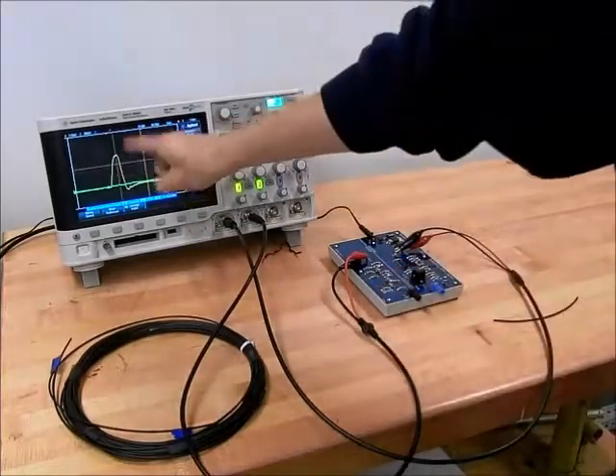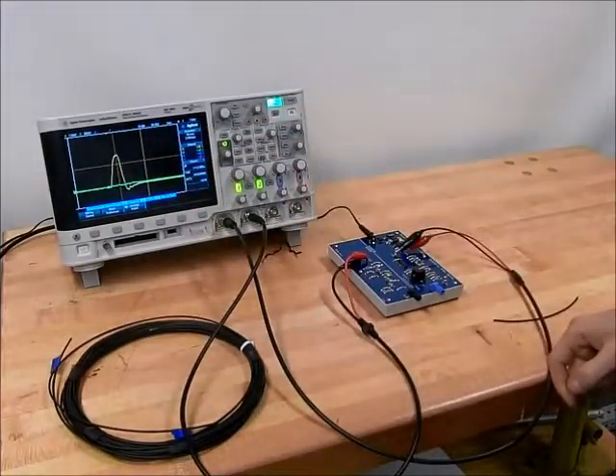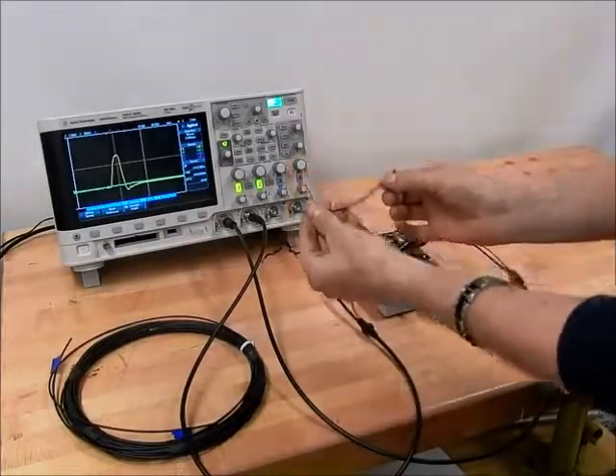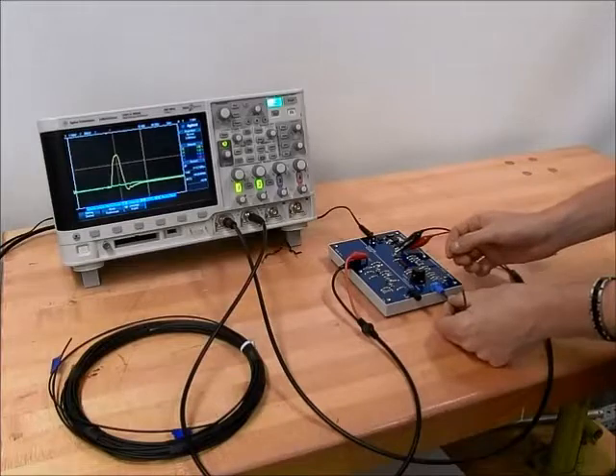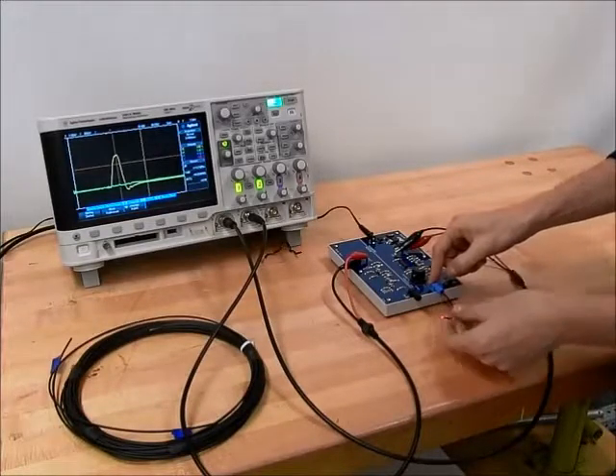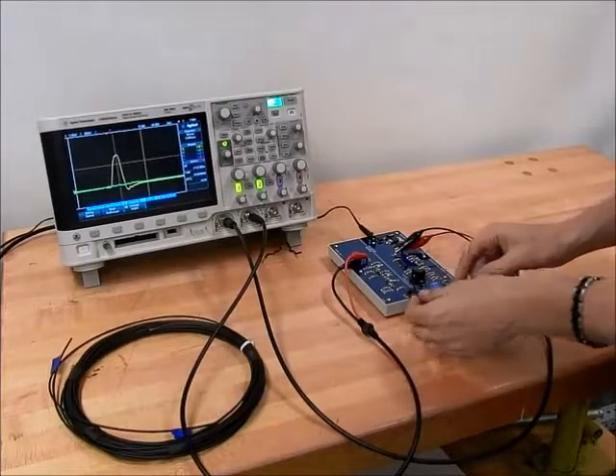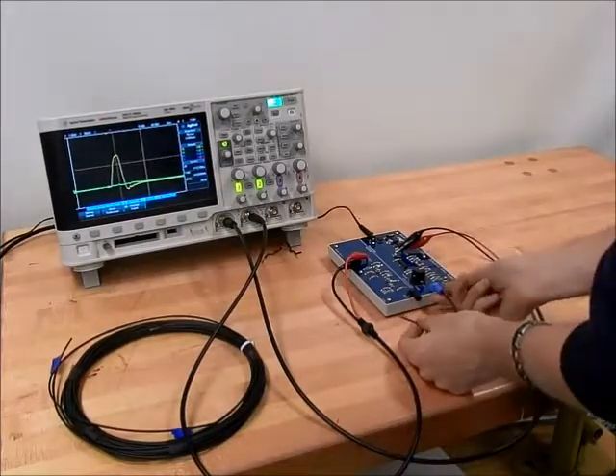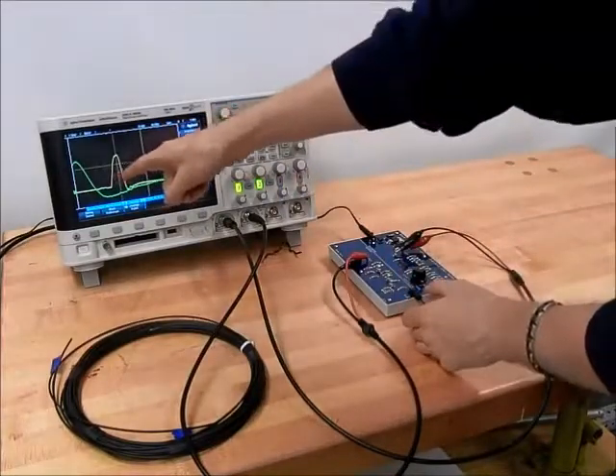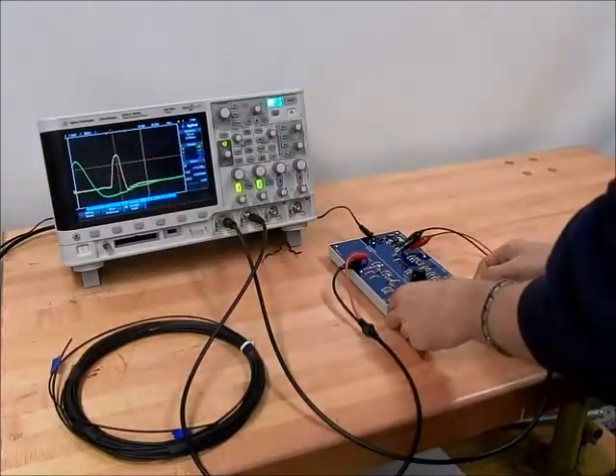There we have our reference pulse. Now to calibrate, take our 15 centimeter fiber optic cable and plug it in to the blue LED port. See LED here, plug the other end here, and now we have our reference.